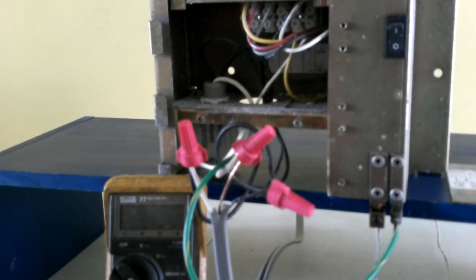If you need to get power on your system and that surge arrestor is the only short causing you a problem, remove that surge arrestor for now, connect your power wires back up, and then go back in and turn your circuit breaker back on and make sure it does not trip again, indicating another short. If everything then turns on fine, that surge arrestor was your short in the power circuit. It's now out of the way temporarily, and you can still run everything because you now have power back. Remember, you will need to replace that surge arrestor as soon as possible.